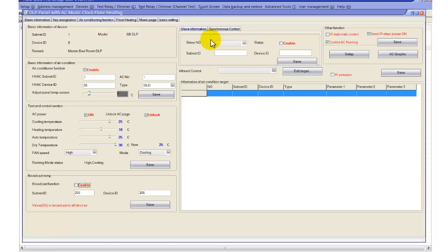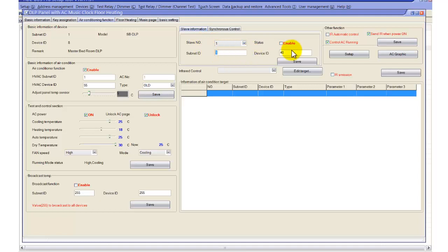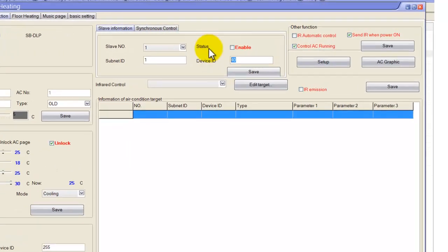Here we have slave information. For example, if you have a child's room with their own AC controller, you can slave their AC page to be shown on your master bedroom DLP, so you can monitor and control that room — see temperatures, check the modes — without going in and disturbing them. You can select AC slave number 1, enter the subnet and device ID of that room's DLP, and pull all that information to your DLP for monitoring.